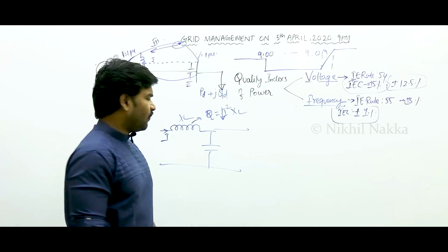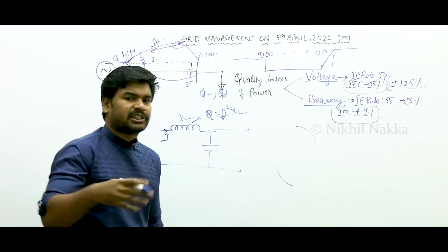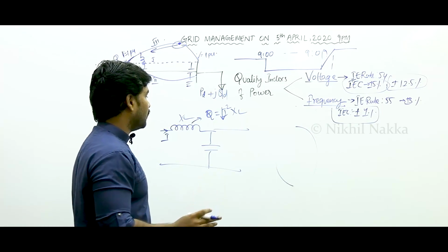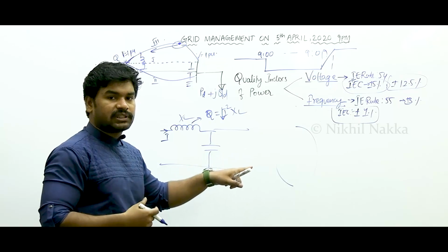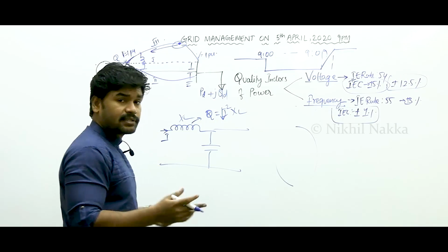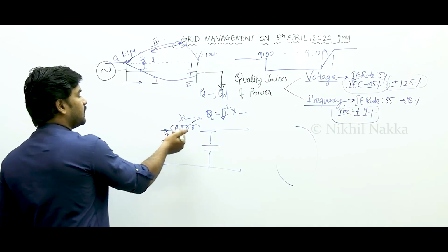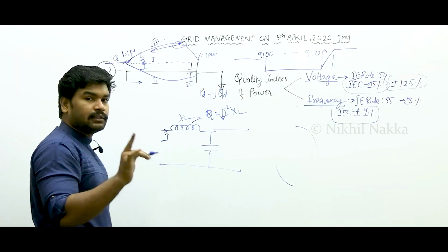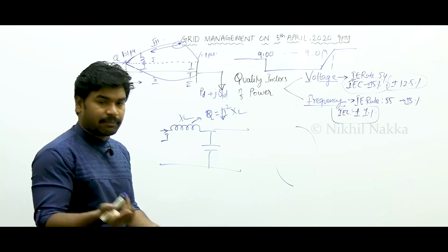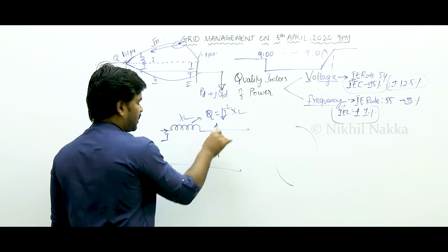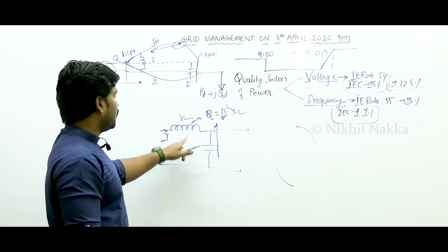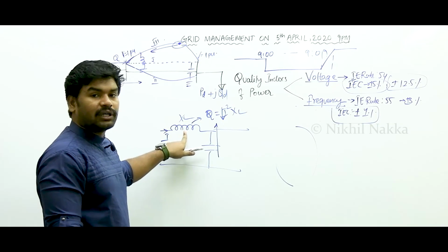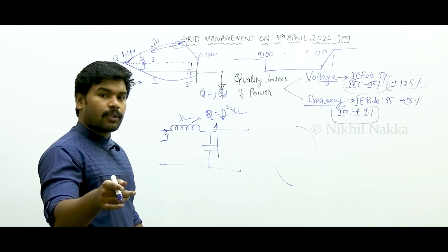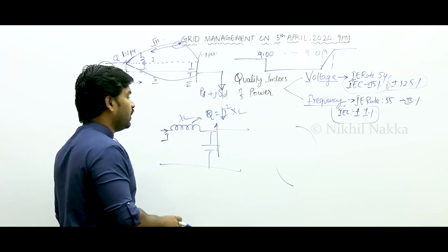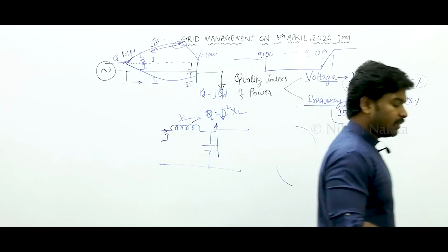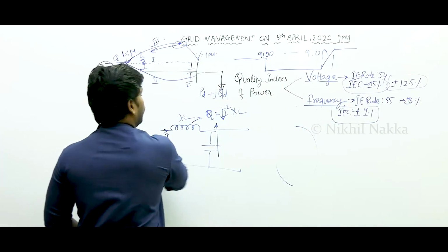If current in the line is decreasing - of course here there might not be much reactive load because industries have shut down - but still current will decrease due to this effect. Yes, current will decrease, and if current decreases, the power consumed by the line will decrease. So this will again create a problem. And anyhow, generation is constant, it keeps on generating. Now there is not even this inductor ready to consume this excessive reactive power. So you cannot make that kind of very hard and harsh statement, right? So I hope your doubt is cleared.